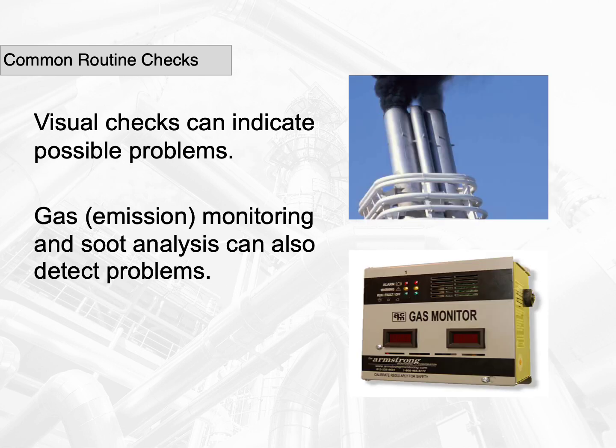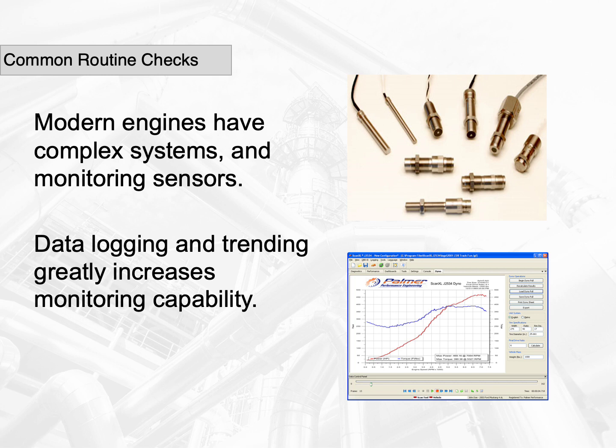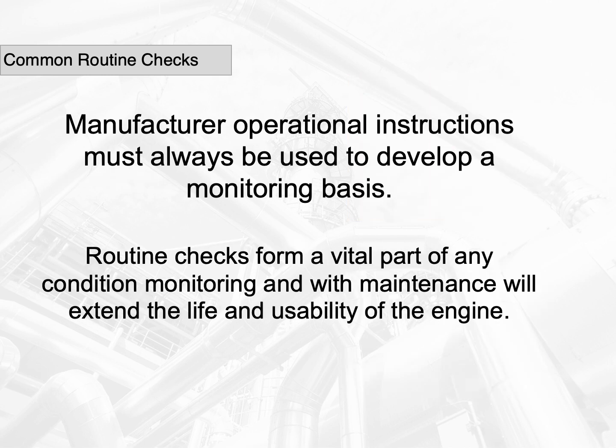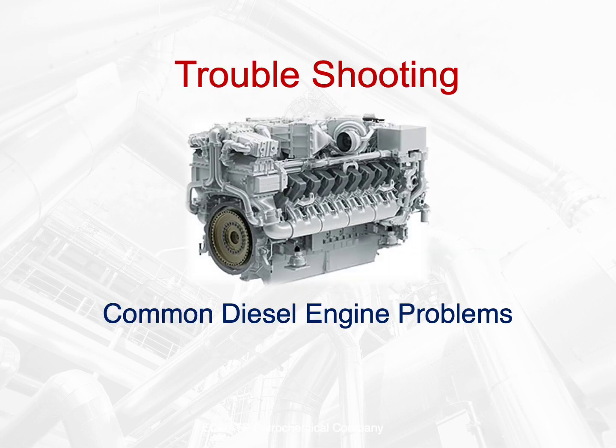Visual checks can indicate possible problems. Gas emission monitoring and soot analysis can also detect problems. Visual indication of serious problems can often be seen in the exhaust flow. Detailed monitoring can identify early problem development. Modern engines have complex systems and monitoring sensors. Data logging and trending greatly increases monitoring capability. Manufacturer operational instructions must always be used to develop a monitoring basis. Routine checks form a vital part of any condition monitoring, and with maintenance, will extend the life and usability of the engine.